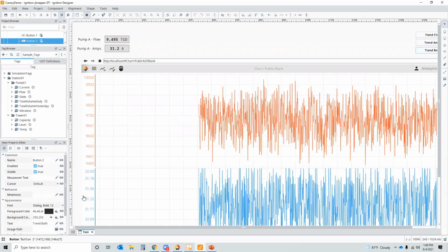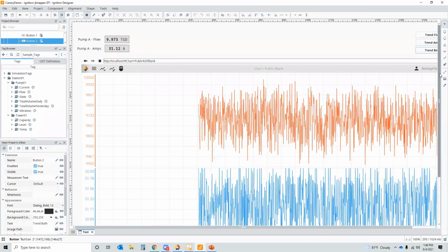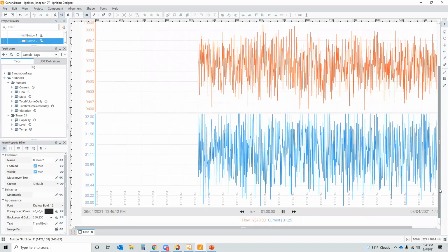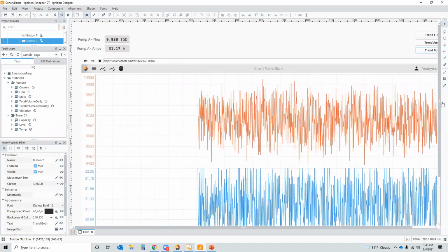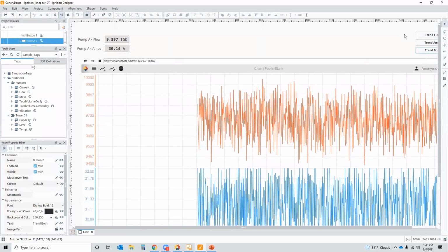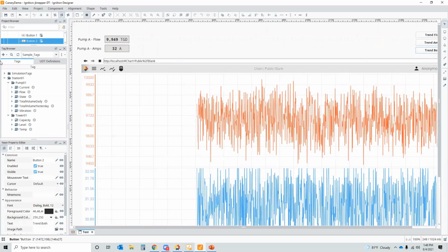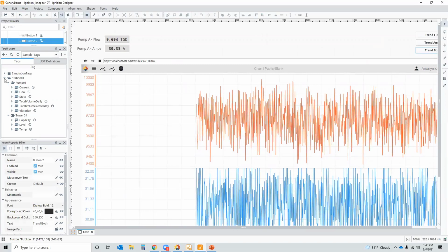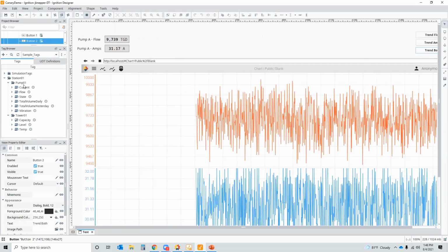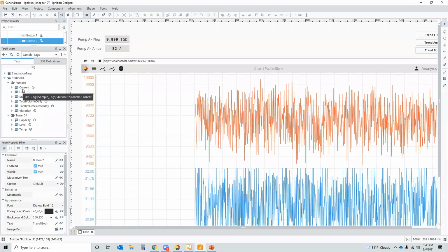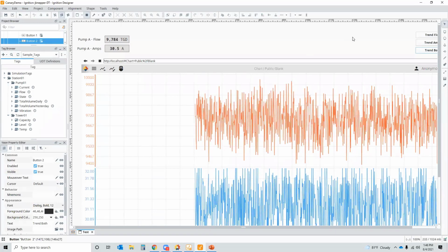And as you can see, I've picked up both tags, and this chart, since I didn't set a time, defaults to an hour in my own personal preferences for my trend chart. So just like that, I can create this scripting call, which means if you know your tag paths, and if you've noticed, it's the exact same tag path. I'm just putting the Canary server name at the front, localhost dot station01 dot pump01 current or flow. And so it becomes very easy to script this and use Axiom as a template for your tags.